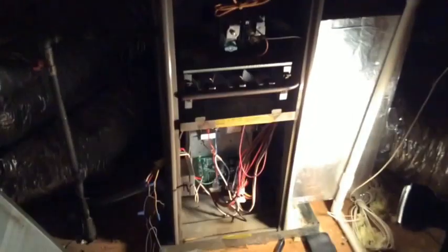Everything looks good here. So let's turn on the power to the unit, and then let's turn on the gas first. So this valve, here we go. And then unit 2. So it's not going to go until it senses that this panel is closed, but I'm just going to close it with my foot. There's power.